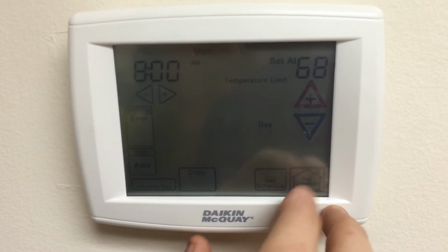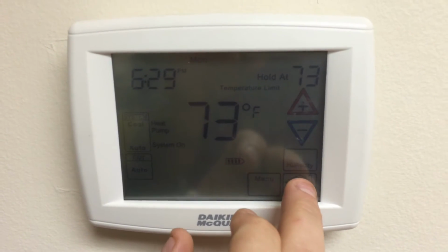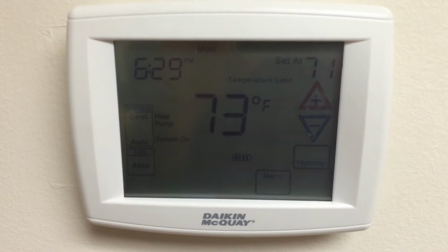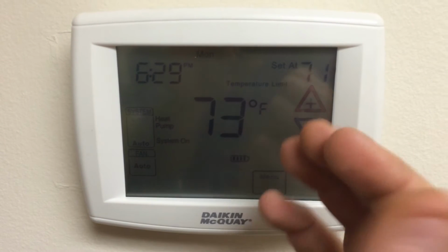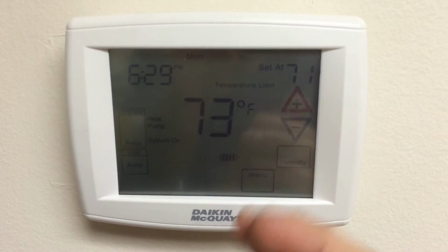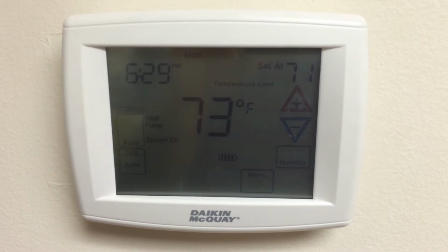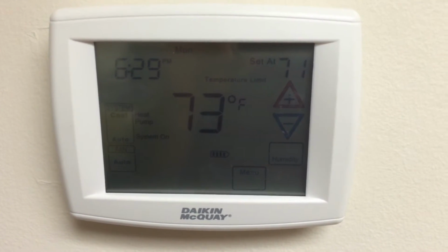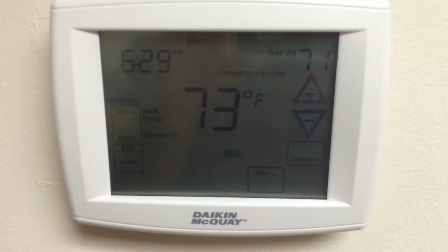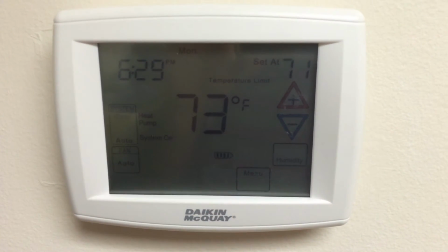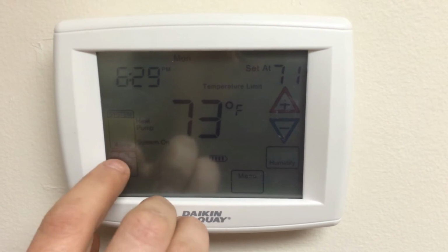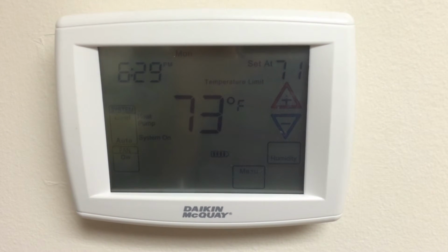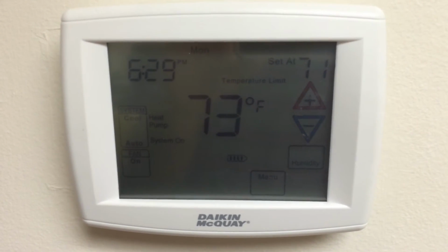Once we have our schedule set, you go back to run schedule. You hit the run schedule button, and it'll start doing its schedule. If you leave it in auto, it will do its own heating and cooling. It'll have to drop a few degrees, but it will eventually switch over to heat, or it'll eventually switch over to cooling, depending on what the building needs. If someone wants to run the fan all the time while the program's going, they can just hit the fan button while they're in the room, and the fan will stay on all the time regardless of whether it's heating or cooling.